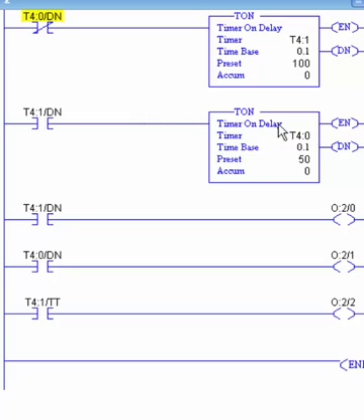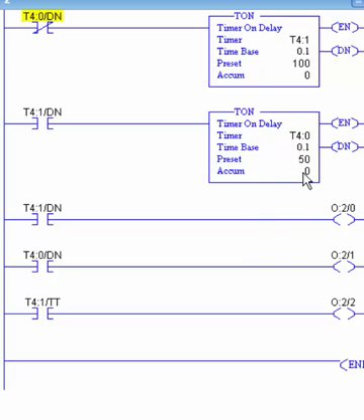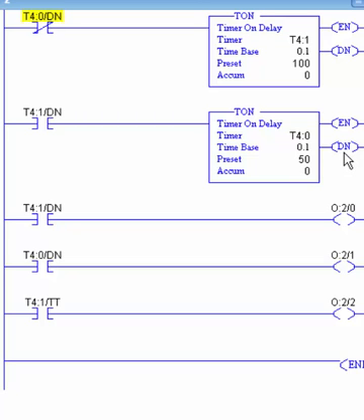When we first start out, T4:0 is not done - and that's what I'm checking for with an XIO: are you not done? It's not done, so this is true, and this timer will start counting up to 100. As soon as it hits 100, that done bit comes on and activates the XIC, starting T4:0 timing. When T4:0 counts up to 50, its done bit turns on, making the XIO false - which resets T4:1's accumulator and done bit. As soon as T4:0's done bit turns off, T4:1 goes false too, resetting everything. Then the XIO becomes true again and the cycle repeats.